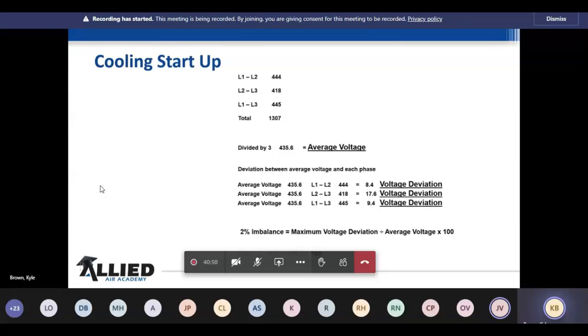Okay, we're going to divide those by 3, and we're going to get the average voltage. So our average voltage for this particular example is 435.6. Now you'll notice there's one voltage kind of low, and sometimes you'll have a high leg. Now there's all different names for that, some of which I can't say on this because we're recording it, but sometimes you'll have a leg that's got more voltage than the other, and I call it a high leg to be politically correct on here.